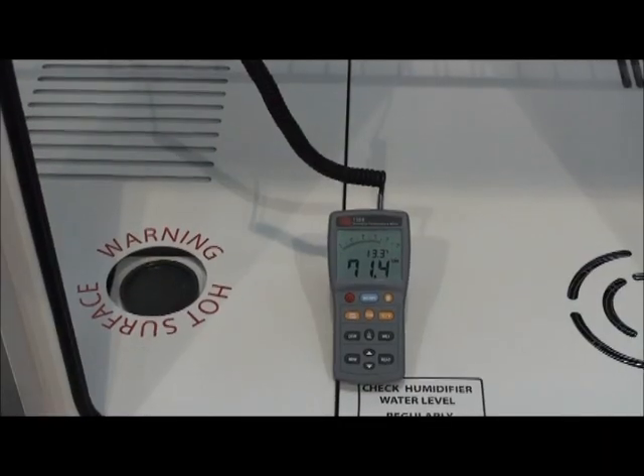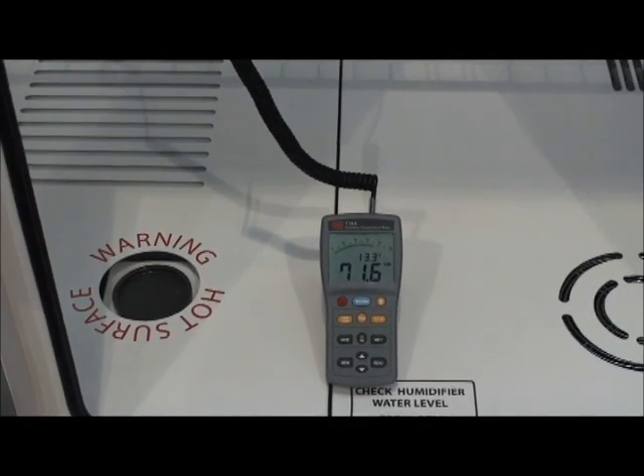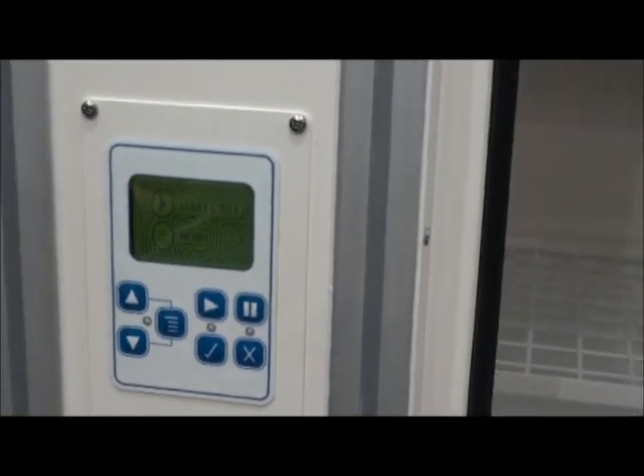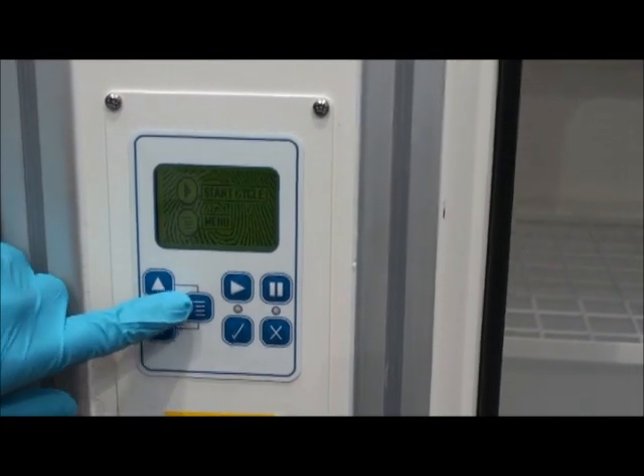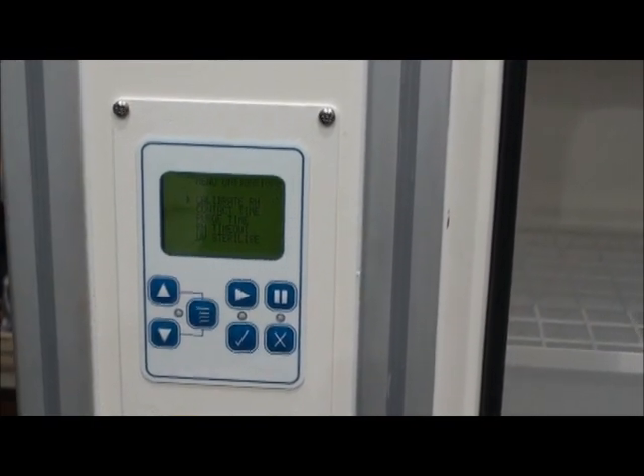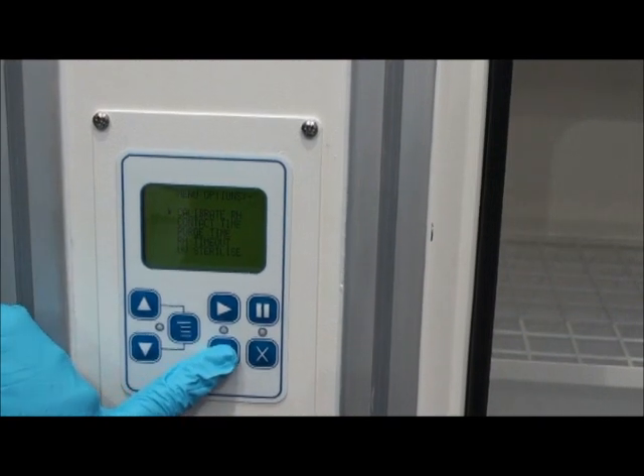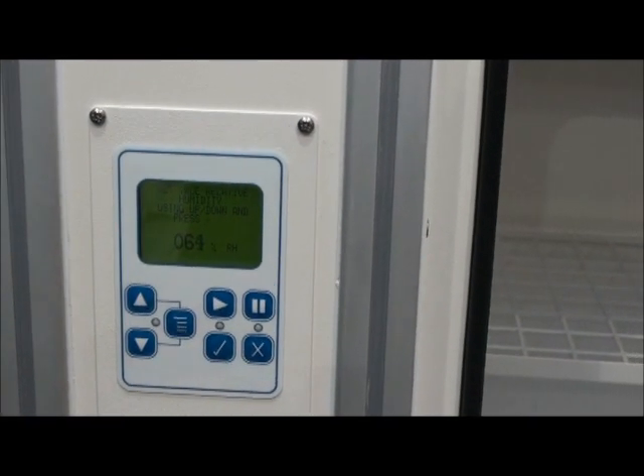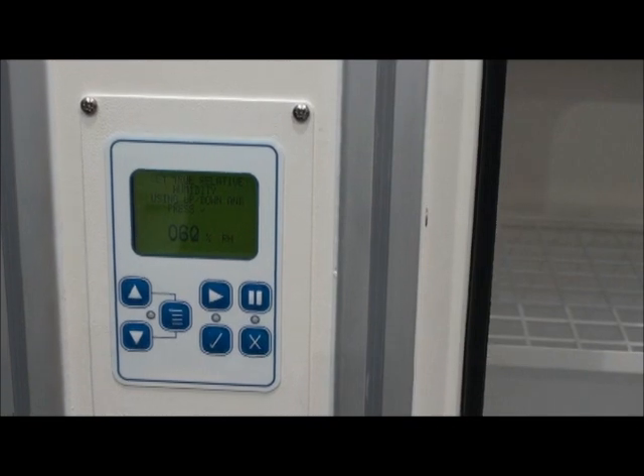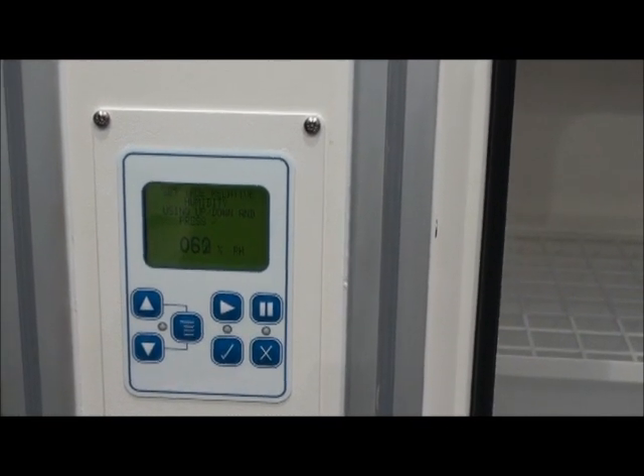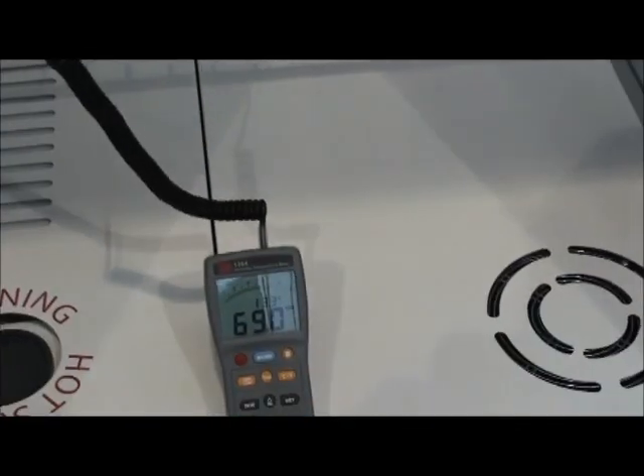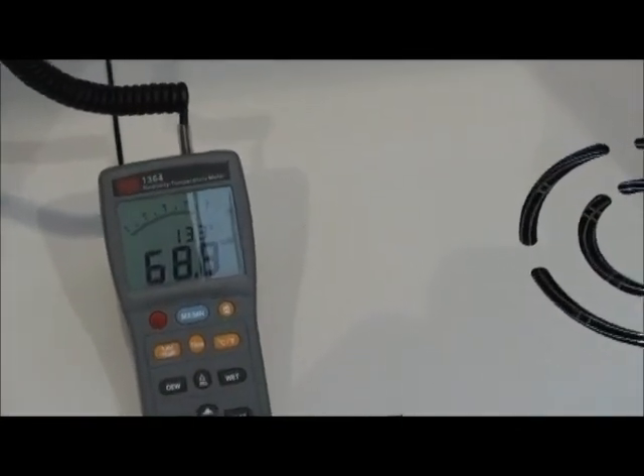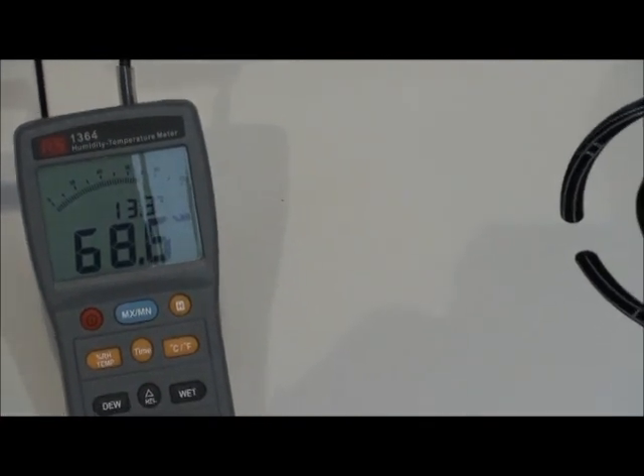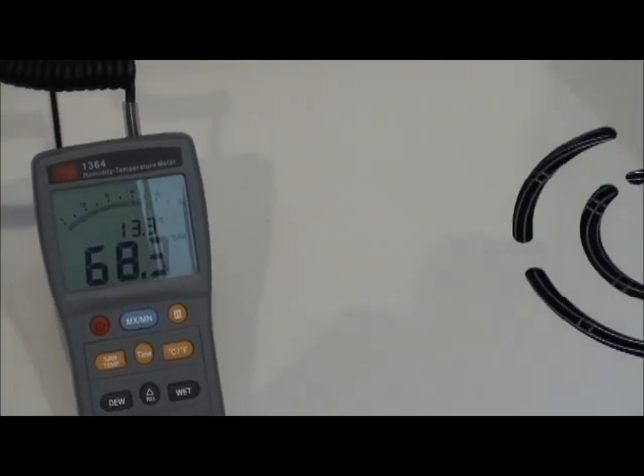Now we're going to go through the calibration of the humidity. Using a calibrated humidity meter, I'm moving to the control panel, pressing the menu key. If you remember, we're going to calibration, so we tick to accept that. Now we're showing a reading at the moment of 60 to 62% humidity. We look at the calibrated meter inside the chamber, and we're showing 69.7. So we're 68.4. It's moving around.